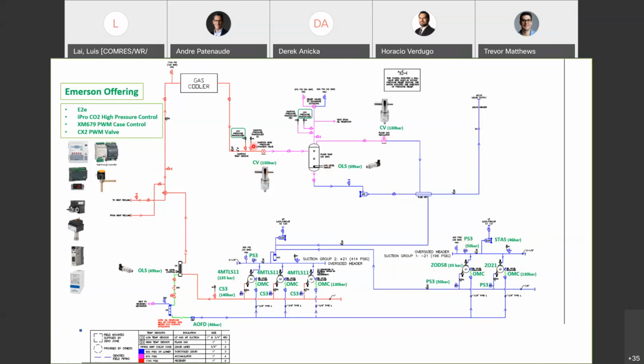We go up here to my gas cooler. We have a high pressure valve coming off the gas cooler, a high pressure valve called a CV valve, and a bypass valve called a CV valve. White Rogers developed something called an OLS. It's an optical level switch, and you can use one for high, you can use it for low. That's available. A liquid line filter dryer, STAS, could be installed here as well, coming off the flash tank. I should have written that on there. And then, of course, you've got drives, case controls, E2, high pressure controllers, and the White Rogers team are developing a North American pulse width modulated valve, or resurrecting an earlier design of a pulse width modulating valve for CO2 type pressures.